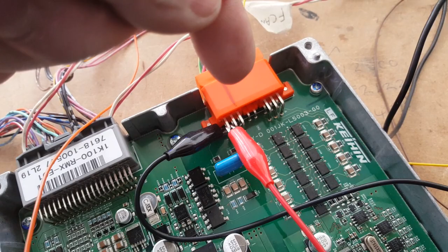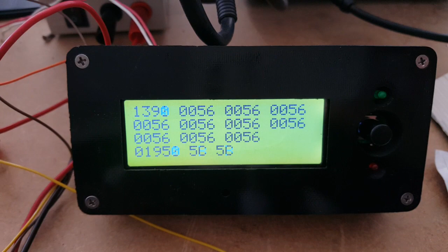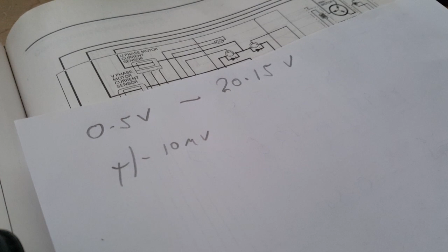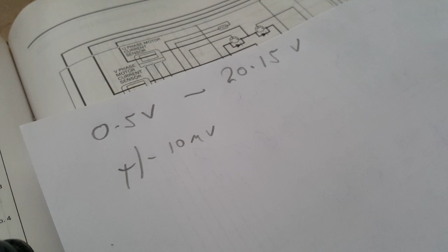At the moment I've got a variable voltage DC power supply just feeding voltage into one of the taps on the battery voltage taps input, and you can see I've got this at 13.9 volts. If you look at the first value on the top left here, we can see it's fluctuating around 13.9 volts. It's got a resolution of 2 decimal points, and it appears to be a 12-bit ADC. The range it allows is 0.5 volts to 20.15 volts on each voltage tap, and the accuracy looks to be about plus or minus 10 millivolts.